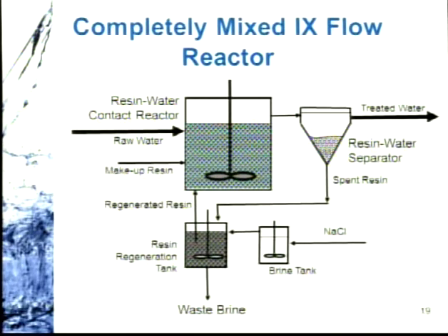Now, this is an old version of a continuously mixed ion exchange flow reactor. I'll leave it to the folks from Orica to give their current version of this, but simply stated, rather than a packed bed column-based application that allows for peaking to happen, all of the resin is simply suspended in a completely mixed reactor, either in an open atmosphere as described by this example, or more commonly for groundwater inorganics, now operated in an upflow pressurized vessel mode.